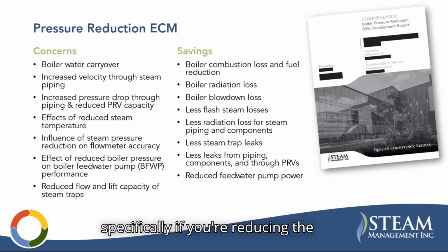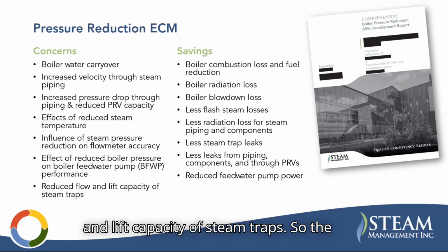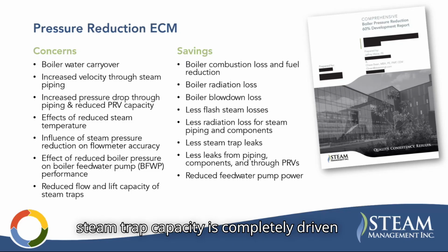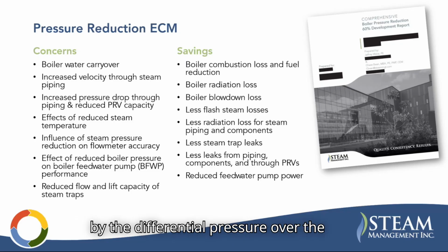Now that's specifically if you're reducing the pressure at the boiler. Reduced flow and lift capacity of steam traps. So the steam trap capacity is completely driven by the differential pressure over the trap. So if you reduce the upstream pressure, you may create condensate return issues.